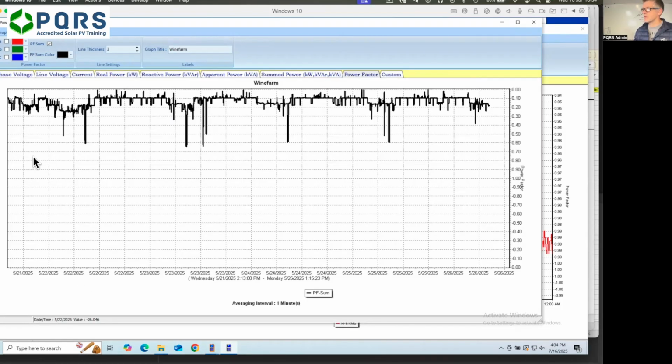This must be one of the worst installations I have ever measured in terms of power factor. So if I look at where the power factor sits on average, it's somewhere between about 0.25 and 0.1, which means that just about all of the power on the site is reactive, and a very small component of the power on this particular site is being used for useful work.